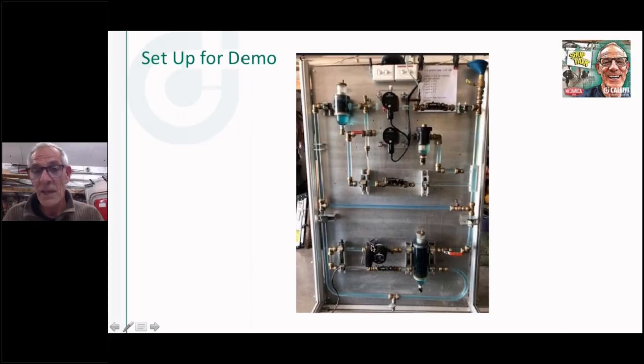with the circulator shut off. Then I'm going to shut this off, and I'm going to squirt some blue food coloring in this side, and I'm going to run this circulator without this one running, and this side is going to get, well, I say blue, it's going to turn purple because there's a little bit of red mixed in here. So this is going to go purple, and this is going to stay red. So it gives you a visual that the two flows, even, you know, by changing the pump speeds, I can rev this one up and down, and you'll see how that separation works.